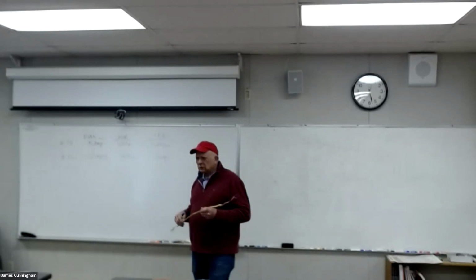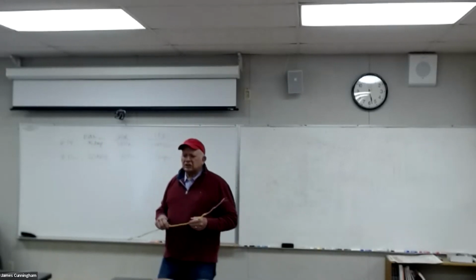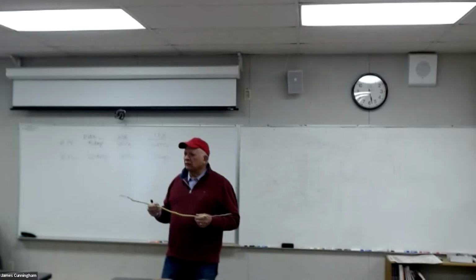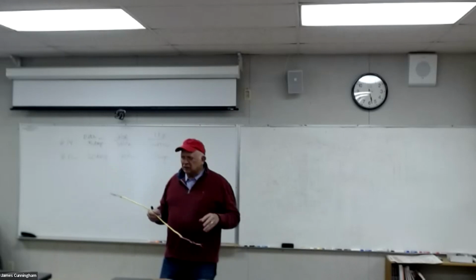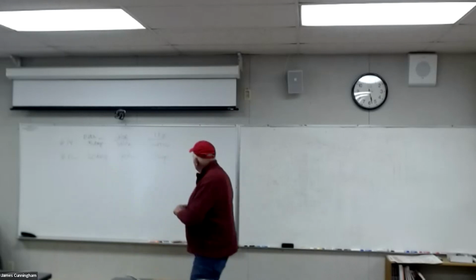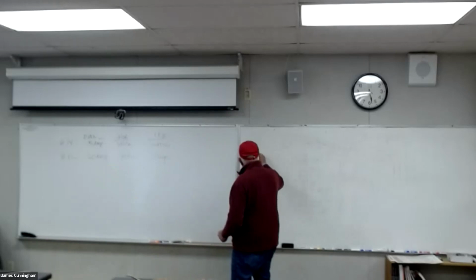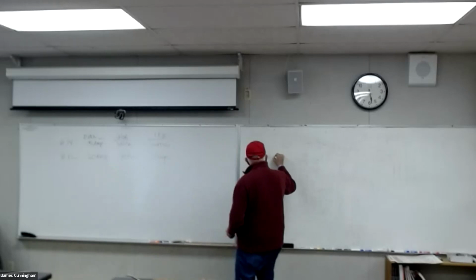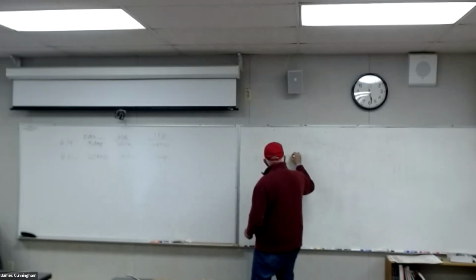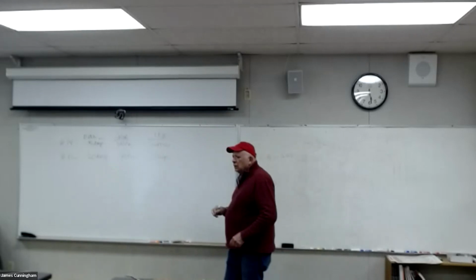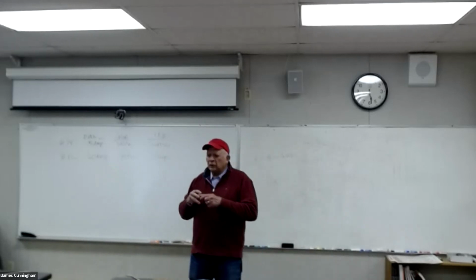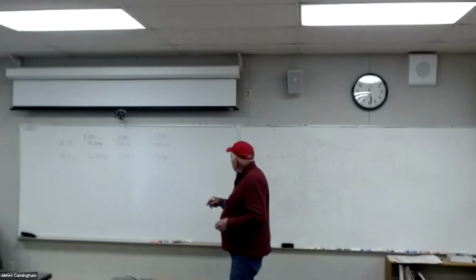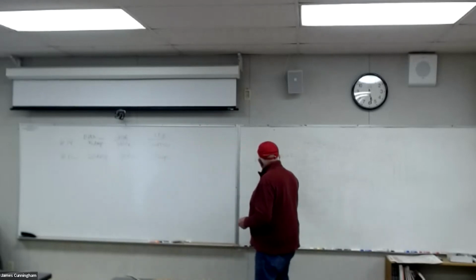most guys don't. What it does is it allows you to have more lights on that circuit if you use number 12. So you can actually, because of the, remember from last week that volts times amps equal watts.